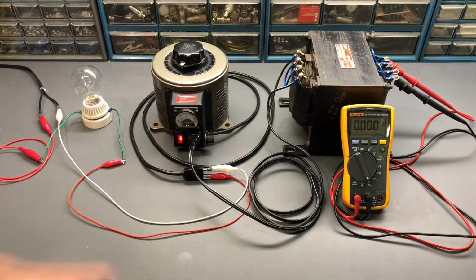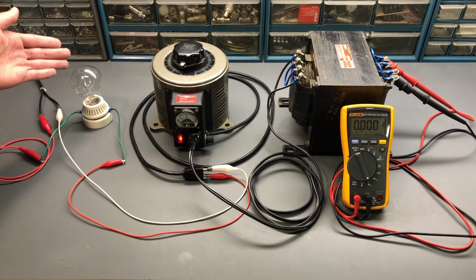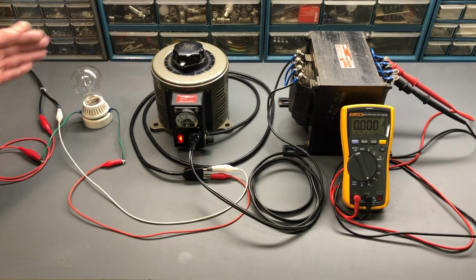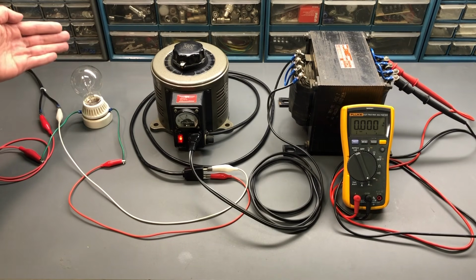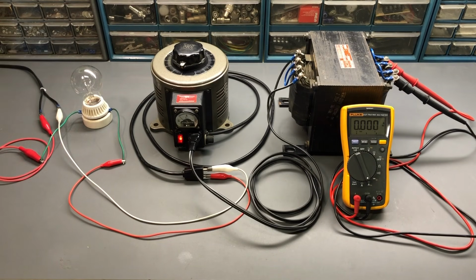You would just be powering the device that you're trying to test. But if something goes wrong and it does short out, we want to know what that current would be limited to. Now, I've already mentioned that the wattage of the bulb does change that current limiting. So in all of these tests, this bulb will remain the same, and it's a 100-watt bulb. And that's a value that you might find is suitable for many types of radios and things like that. But this could be increased to, say, 300 watts, or maybe something as small as 25 or 60 watts.